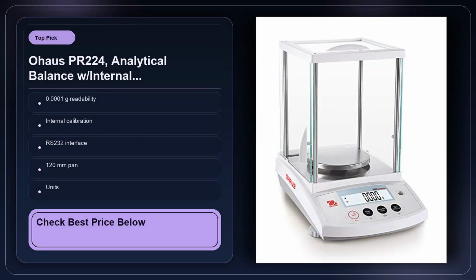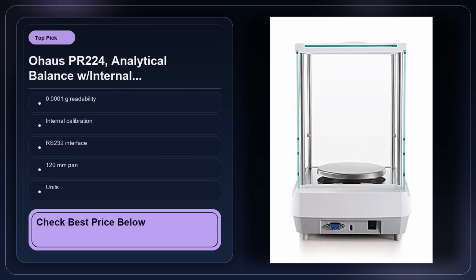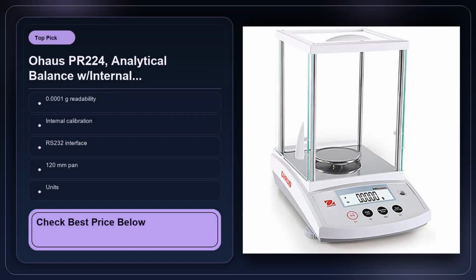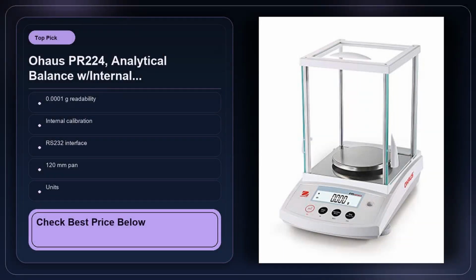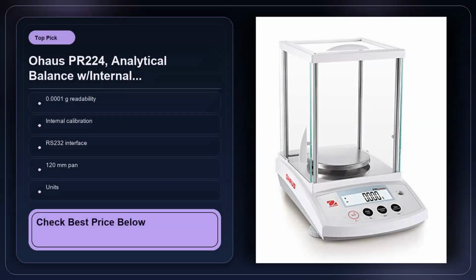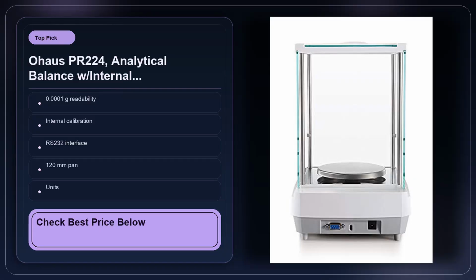Another practical consideration is the environment sensitivity. Analytical balances are notorious for being finicky about drafts, vibrations, and temperature swings. The PR224 does a decent job of self-calibrating, but it won't magically cancel out a draft from an open door or a vibrating centrifuge on the same bench. Users have reported needing to place the balance on a dedicated anti-vibration table or at least on a solid, level surface. If your lab space is cramped and you share benches with equipment that hums, you may need to budget for that extra isolation platform.